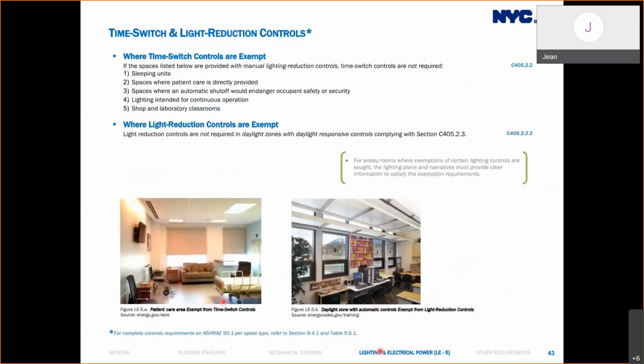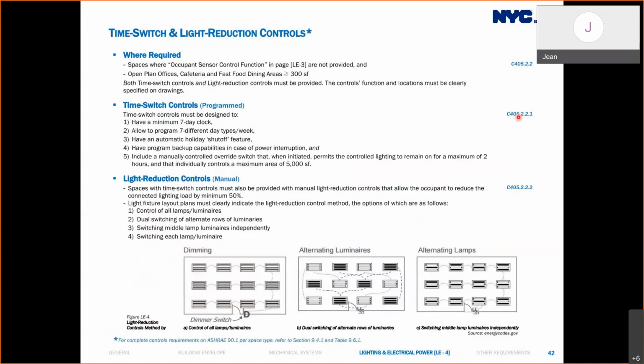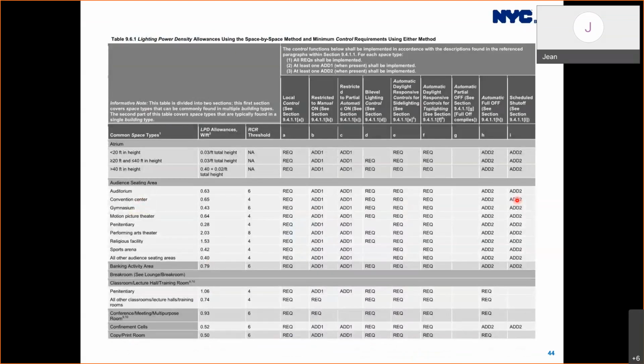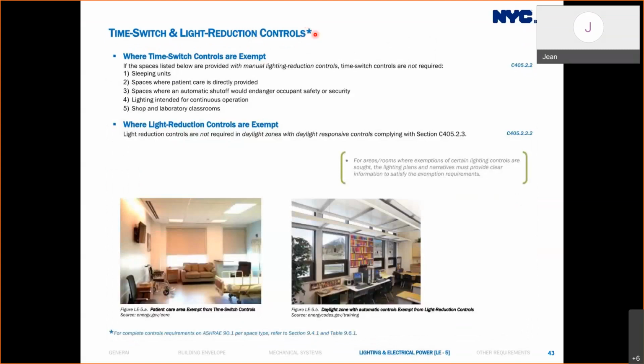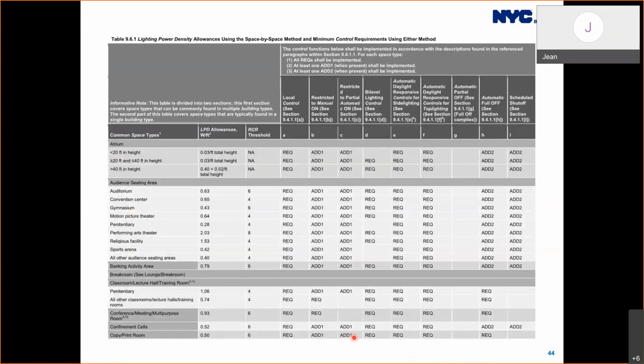Page LE5 lists where time switch controls are exempt and where light reduction controls are exempt. And I'd like you to note that on all these pages, we focused on the ECC section because there is a slight difference between ECC and ASHRAE. So we based most of this lighting controls section of the how-to guide on ECC.